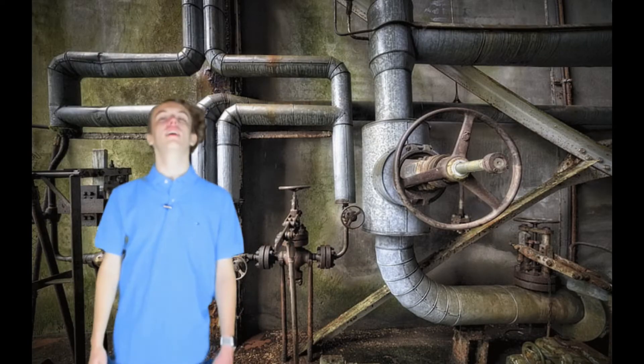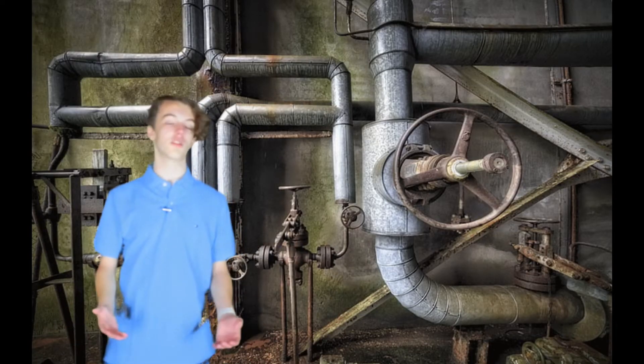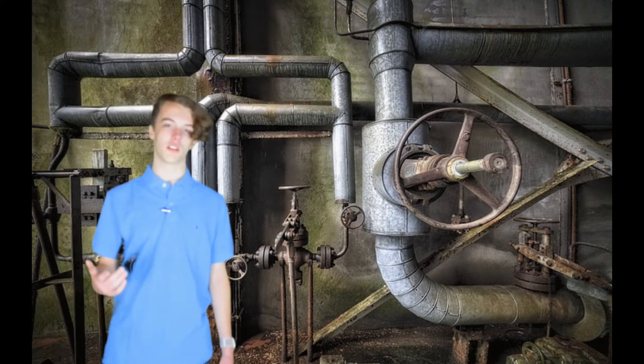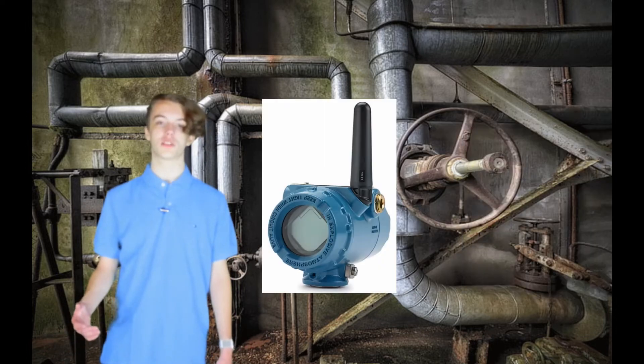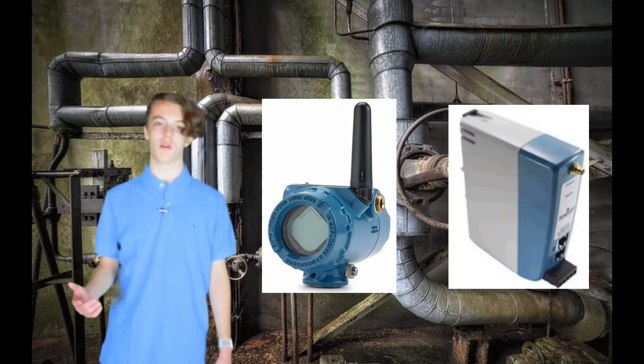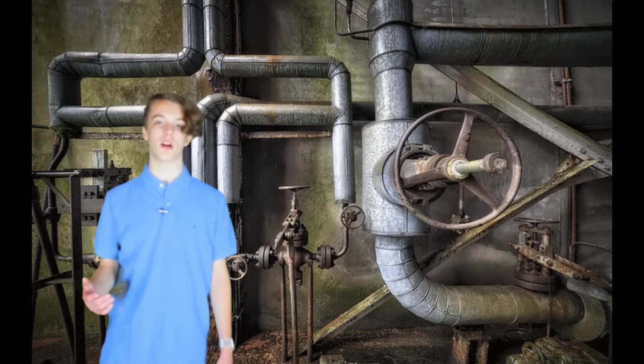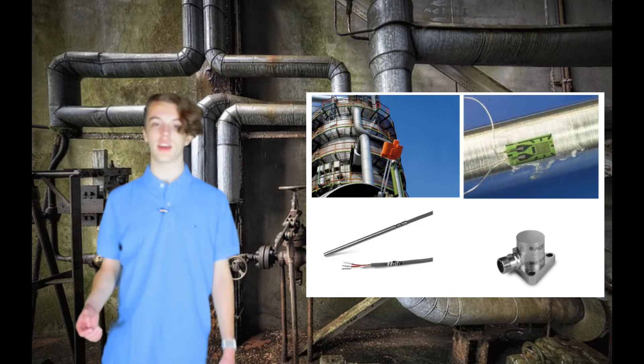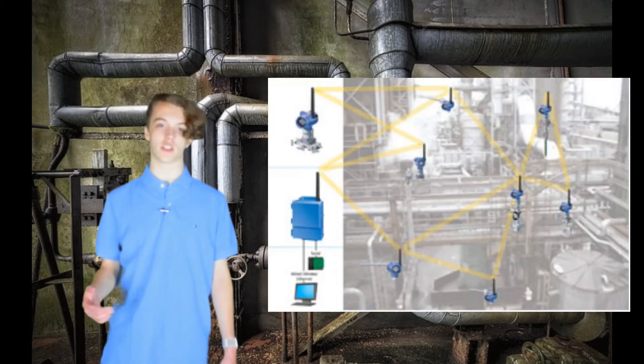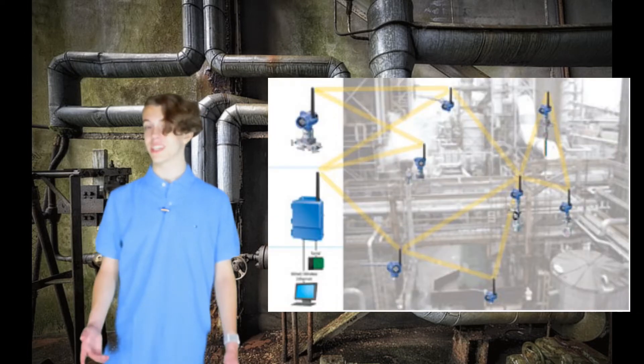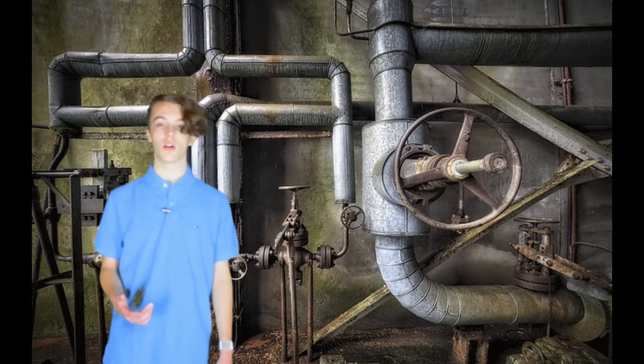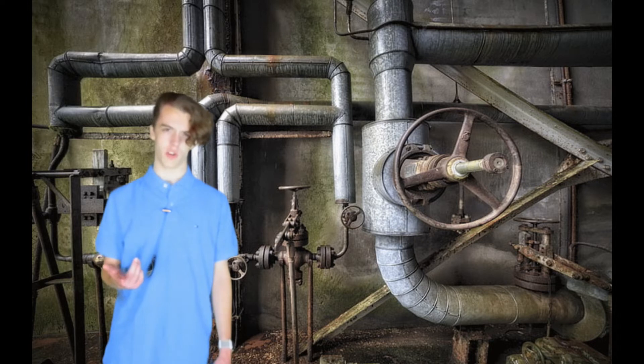If a pipe or vessel starts to get too thin, you can establish ad hoc wireless monitoring. Emerson's Rosemount wireless transmitters combined with their 1410 wireless gateway allows you to set up sensors where you want to monitor all the time. You can then daisy chain the transmitters all the way back to your office. Here's the catch: just measuring the thickness remotely doesn't help you over the weekend when you're not at your desk. You need to log the data for later review.